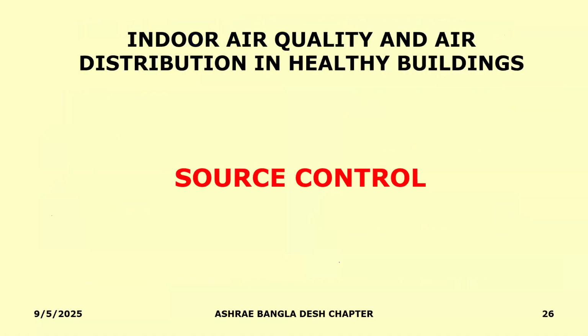So what is the best way for us to make sure that we are able to improve our quality of air inside? First is source control, which means we must identify the source of your pollutants. So when you do continuous monitoring and you're able to measure the various parameters like VOCs, PM 2.5, CO2, etc., and if you are able to arrive at a pattern, and then if you're monitoring it widely, you will be able to decide and arrive at what the source is. And the best way to reduce pollution is to eliminate the source. Of course, it might not be possible for us to do that all the time. So what are the other alternatives?